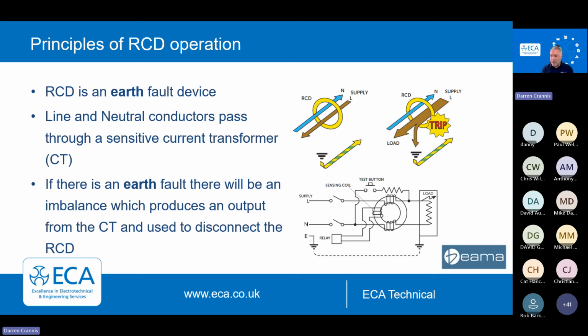And if there is an imbalance, and that could be 30 milliamp, it could be 100, it could be 300, it will trigger a relay to open up the contacts on that device, whether that's an RCD, an RCCB, or an earth leakage circuit breaker. It will actually disconnect the circuit.